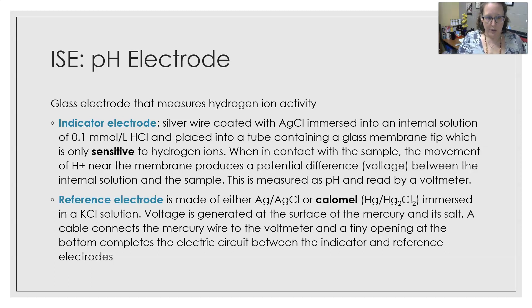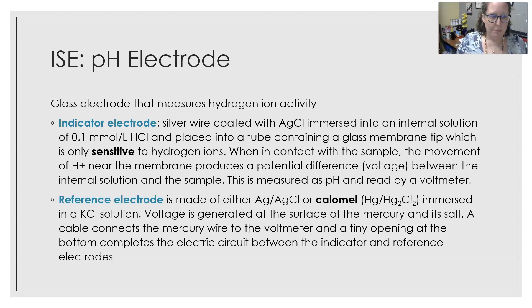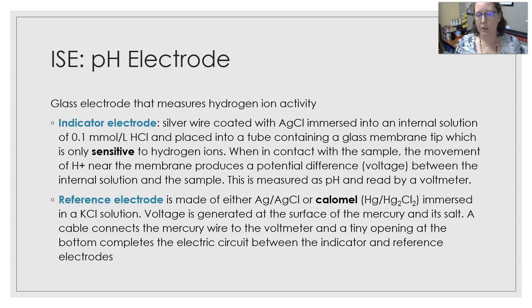This is measured as pH and read by a voltmeter. The reference electrode in the combination pH electrode is made of either a silver wire coated in silver chloride, or calomel — which is mercury coated in a mercurous chloride solution — and it is immersed in a potassium chloride solution. The voltage is generated at the surface of the mercury and its salt. A cable connects the wire to the voltmeter, and a tiny opening at the bottom of the reference electrode completes the electric circuit between the indicator and reference electrodes so measurements can take place.